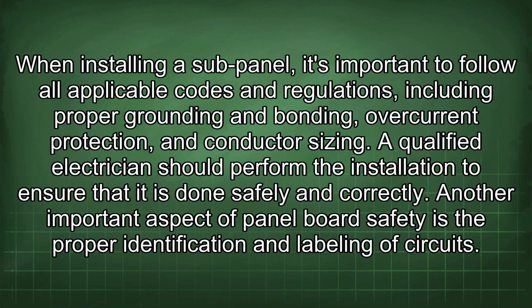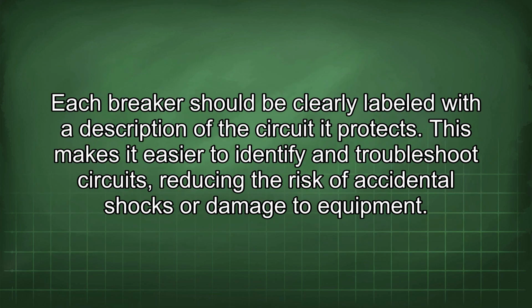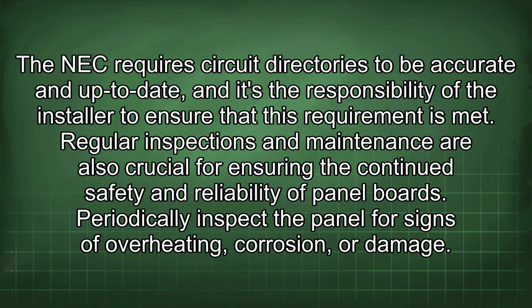Another important aspect of panel board safety is the proper identification and labeling of circuits. Each breaker should be clearly labeled with a description of the circuit it protects. This makes it easier to identify and troubleshoot circuits, reducing the risk of accidental shocks or damage to equipment. The NEC requires circuit directories to be accurate and up to date, and it's the responsibility of the installer to ensure that this requirement is met.